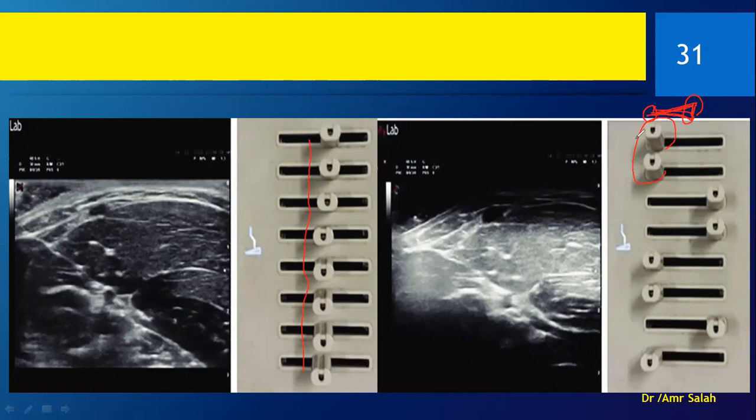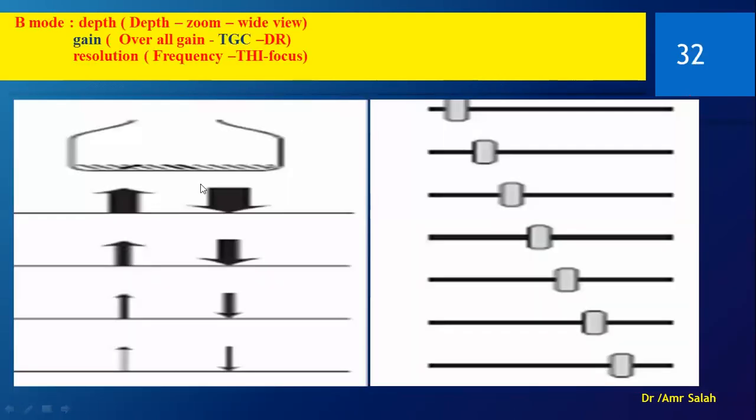So just this is why I am drawing it, in order to remind you that this is how my machine is put. So here, when the two sliders are in the maximum narrow end, in the black end, what happens? No picture. Now when the two below are in the maximum bright end, what will happen? White, absolute brightness. Now these are black, and the other way white, and this black. We are playing around in order to show you how you can control each sector by these two little sliders.